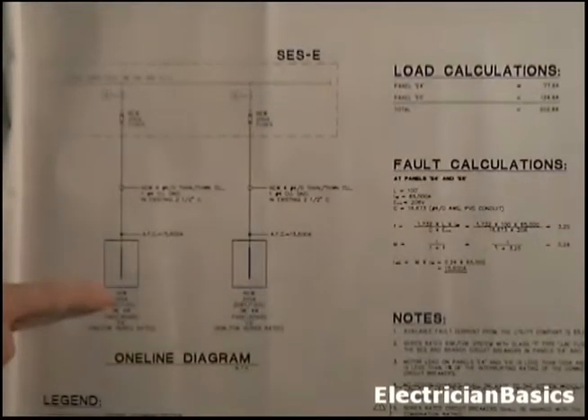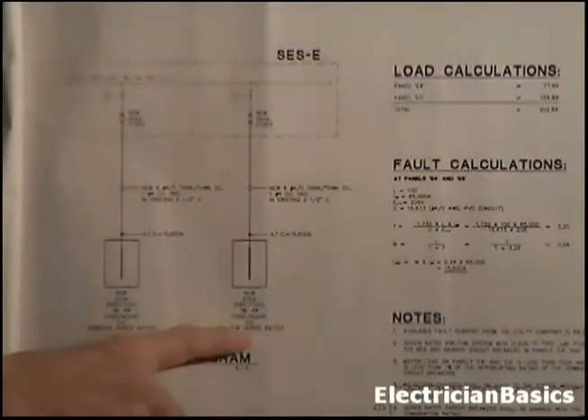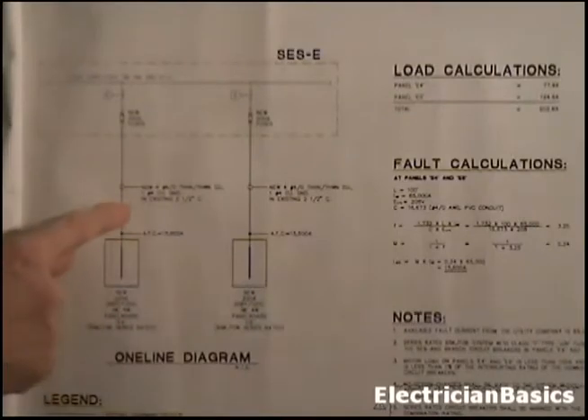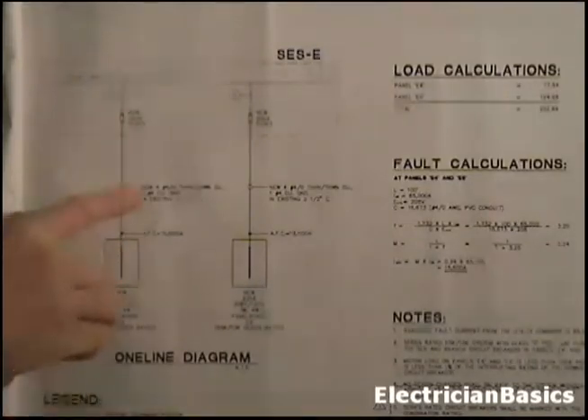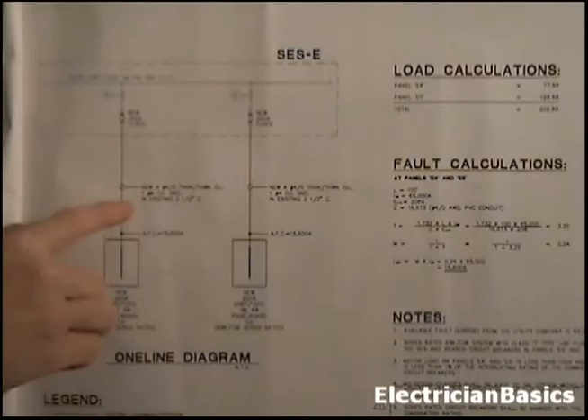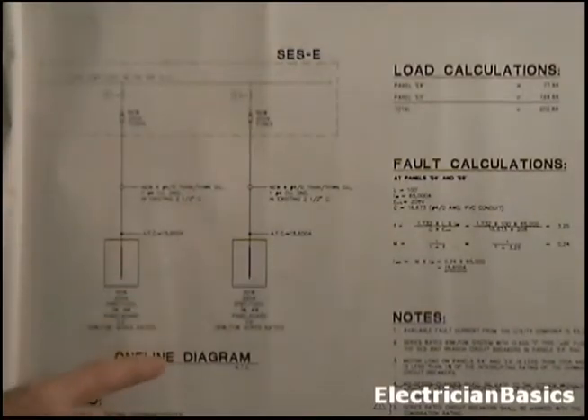Now down here it tells what type of panel: 225 amp, 208, it's a Y configuration as opposed to a delta configuration, 120 volt, 3-phase, 4-wire panel board, and it's E4, and this panel is E5. Now if we had any kind of disconnect in here, it would have to show that. If we had, let's say, a transformer, sometimes you do that, you have a transformer before the panel, the transformer would be on here. If you had a transformer after a panel, you would have the panel, then the transformer, and then a panel after the transformer.